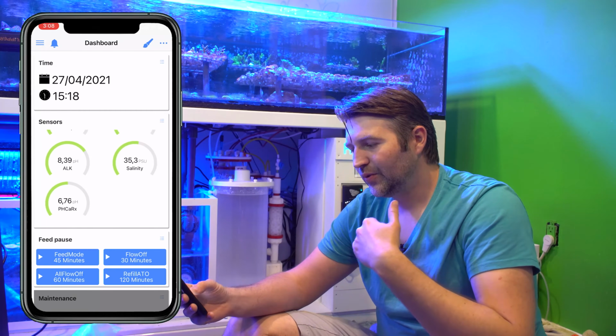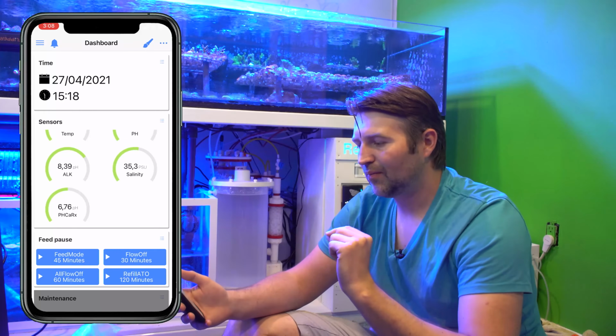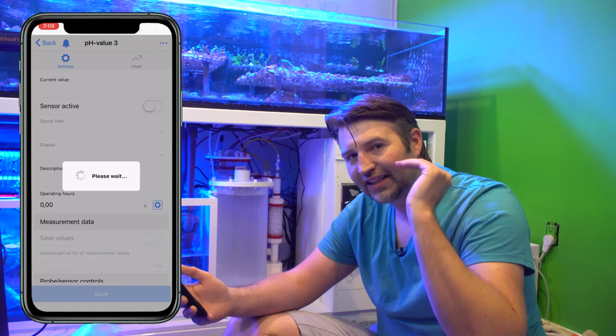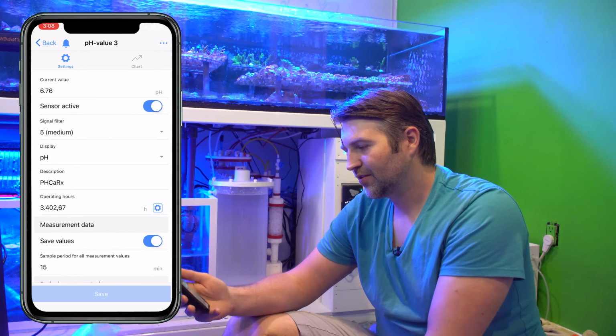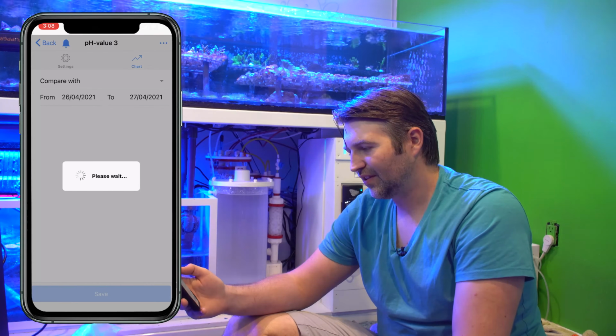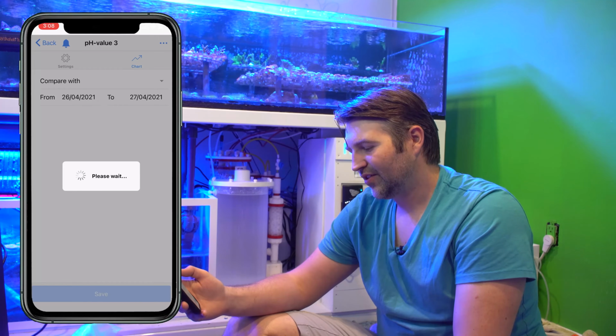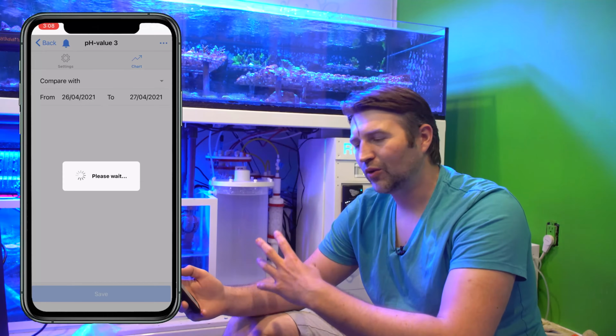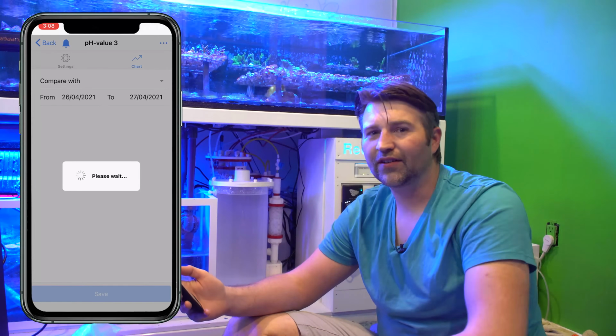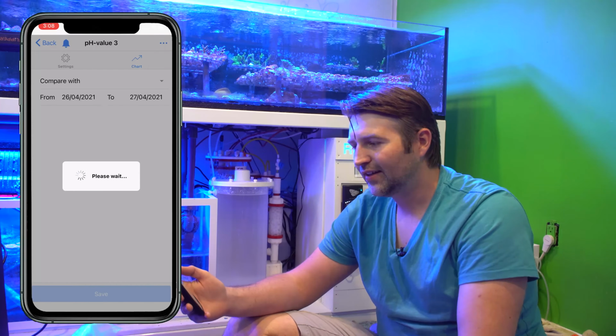Now, I also like to tune it in a bit more so there are fewer cycles on it and it keeps pretty stable on its own. So we go into the chart, we should be able to see those little peaks and valleys. This step isn't required because the probe and solenoid are really doing the work, but if you dial it in so it just constantly stays on, there's less wear and tear on the solenoid and the outlet, and I find that's just a little better for longevity.